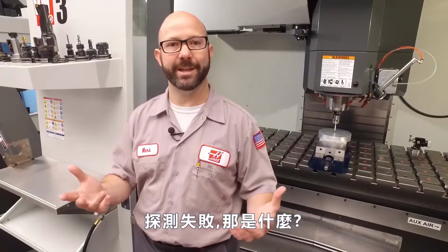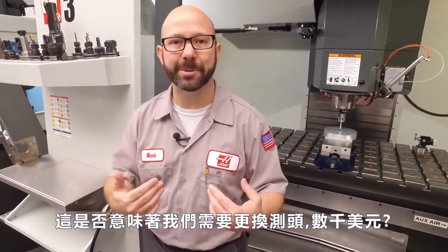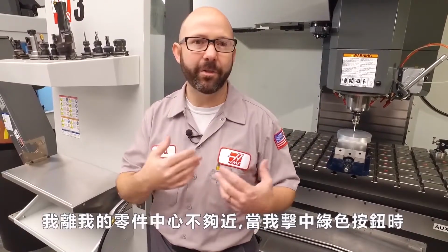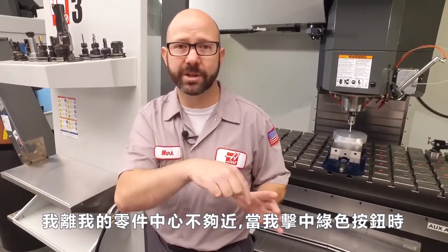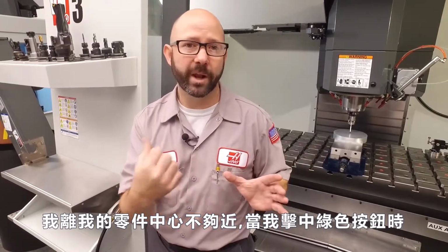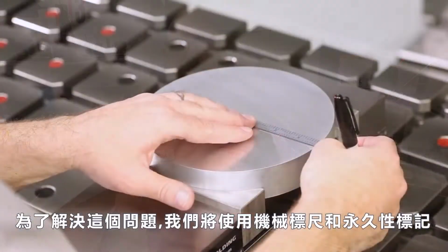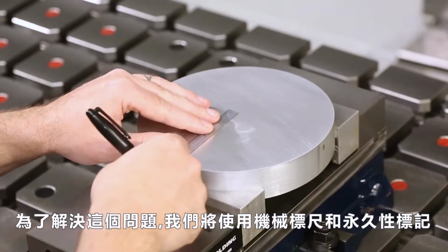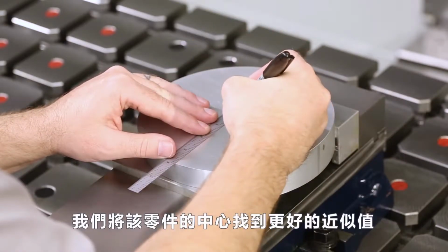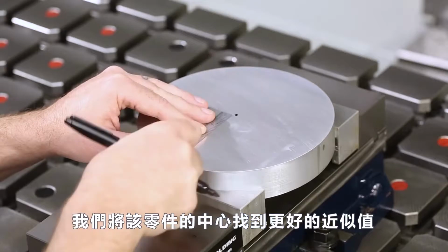Probe fail, what is that? Well, does that mean we need to replace the probe? Thousands of dollars? No. The root cause is a lot less sinister than that. All this meant was that I wasn't close enough to the center of my part when I hit the green button. Now to fix this, we're just going to use a machinist scale and a permanent marker. We're going to find a better approximation for the center of that part.